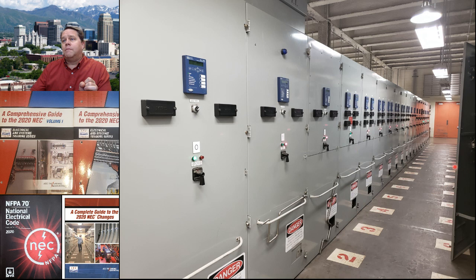What if I have both doors across from each other open at the same time? The code does not give us relief for that. I would have to add at least another 5 feet between these two pieces of equipment. And in this room, this is not the only little corridor of switchgear. This room would probably need to be, and I'm being serious, probably 30 feet bigger to satisfy this new requirement.